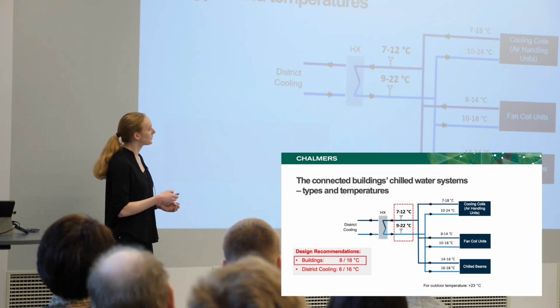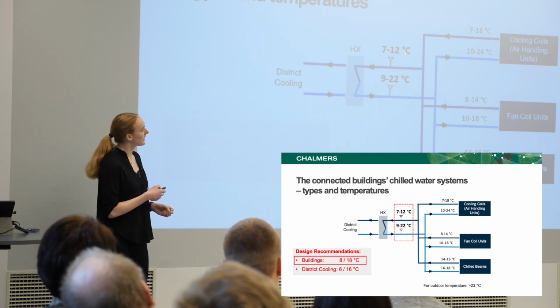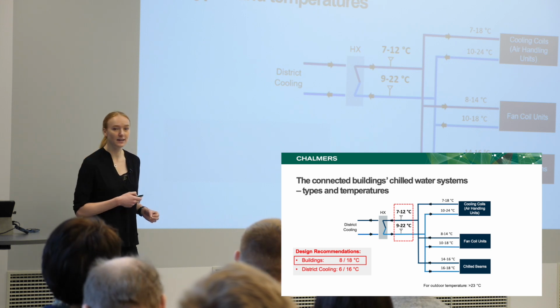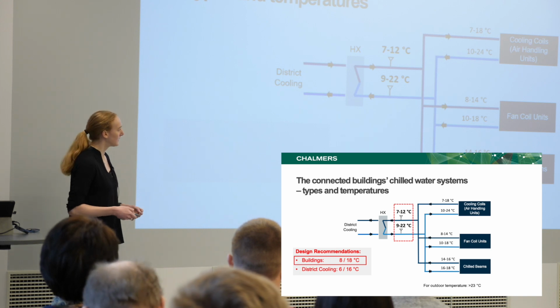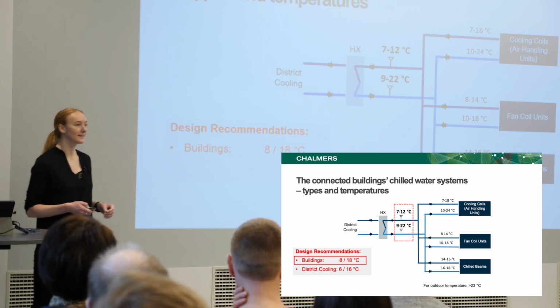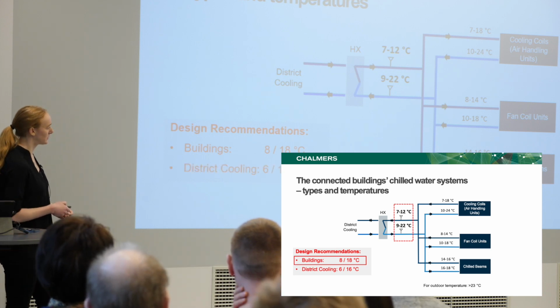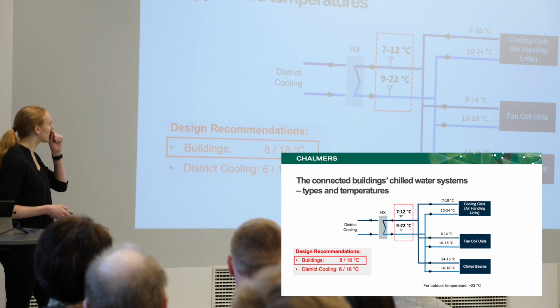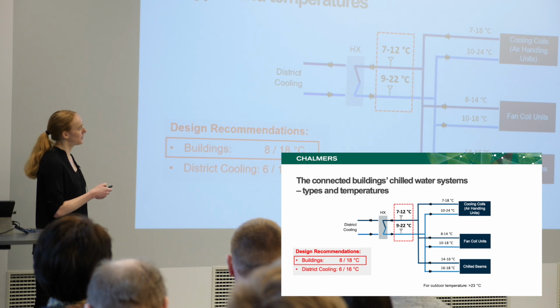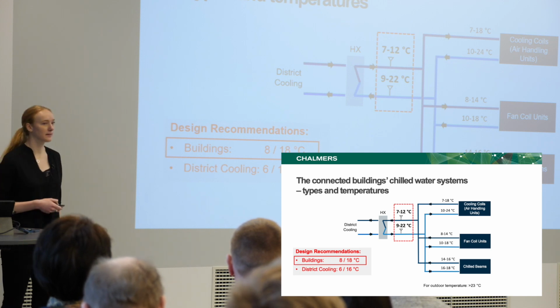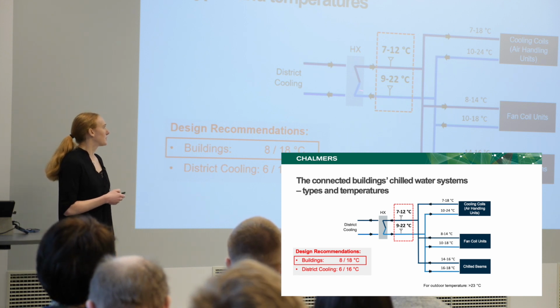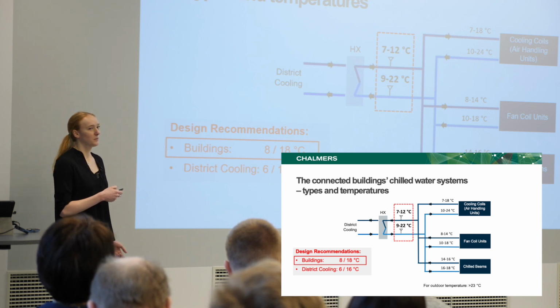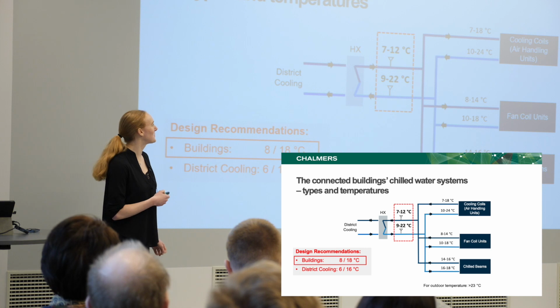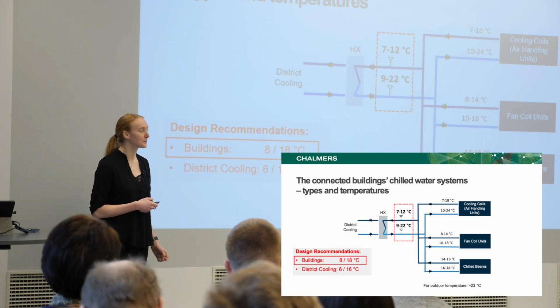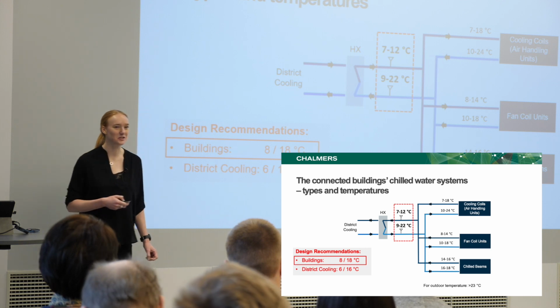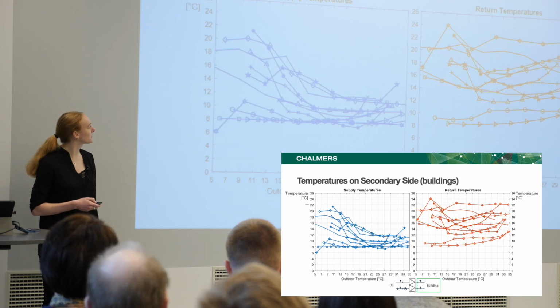And all these temperatures together for all the 37 buildings, this is what the aggregated supply is just on the secondary side of the heat exchanger, and also the return temperature. And then we can compare these temperatures to the design recommendations I mentioned before, and also what the district cooling temperatures are on this side of the heat exchanger. And then we can see that the actual temperatures deviate quite a lot from the design temperatures. What sticks out the most is that not everyone uses 8 degrees. Well, some use actually lower, which is quite okay. But some actually use a lot higher temperatures in the summer. And the return temperature always, of course, is an issue, which I will come back to, or which I will show here actually.